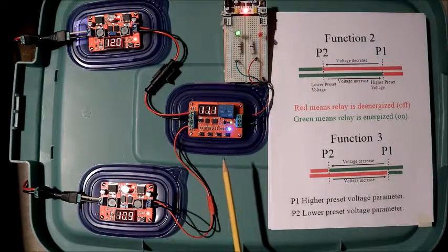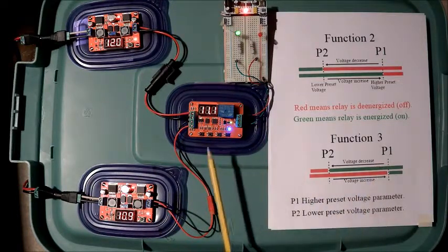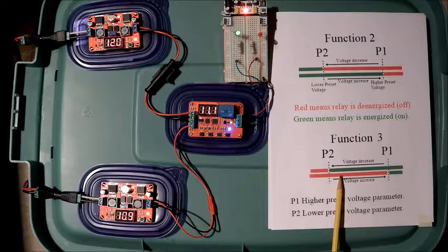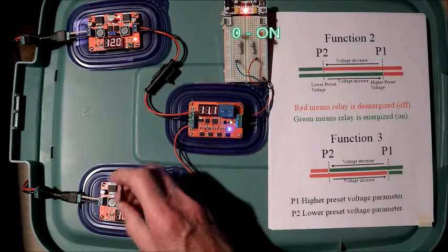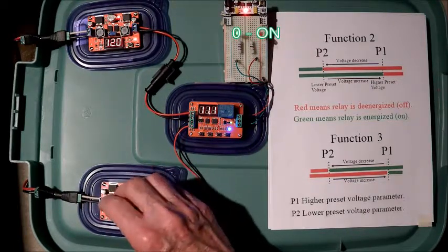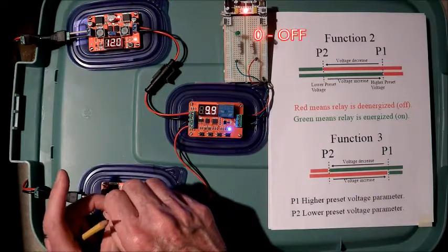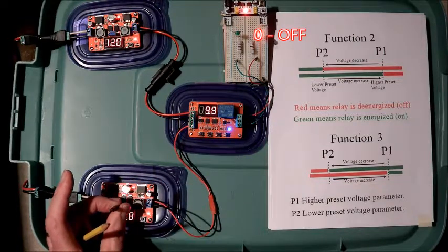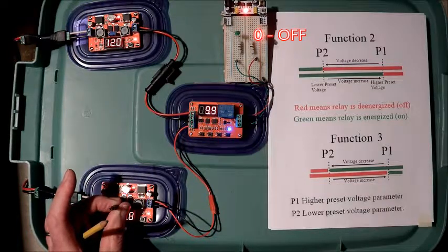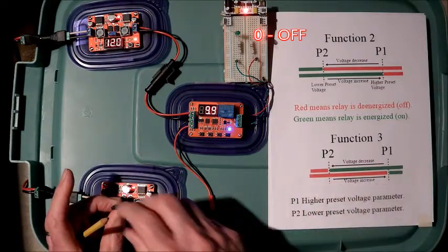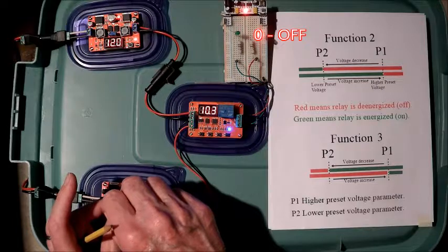In Operational Mode, I'm above the preset, higher preset value. I'm above the lower preset value. The relay is energized. Green light being on. Decrease the voltage. 9.9. Voila. The energized relay de-energizes. Turns off. It will remain off. The relay will remain off until I hit the high preset value.